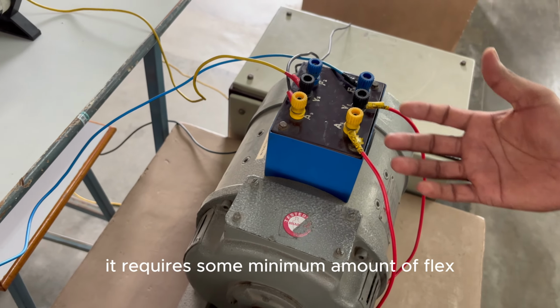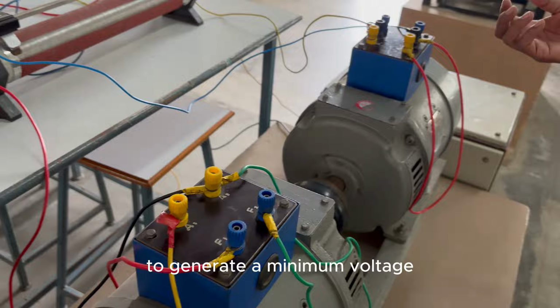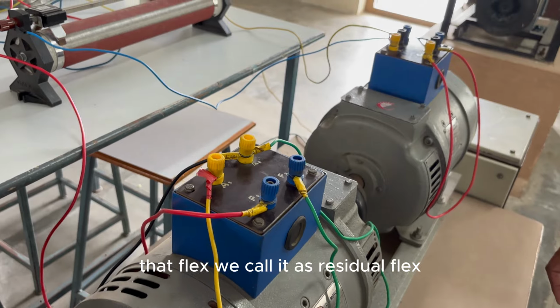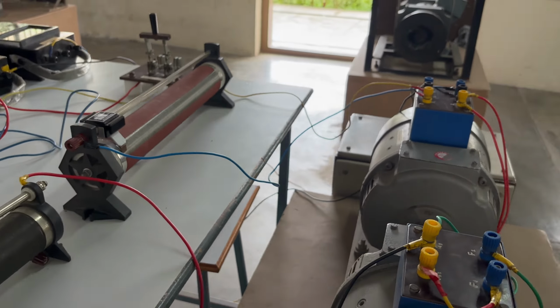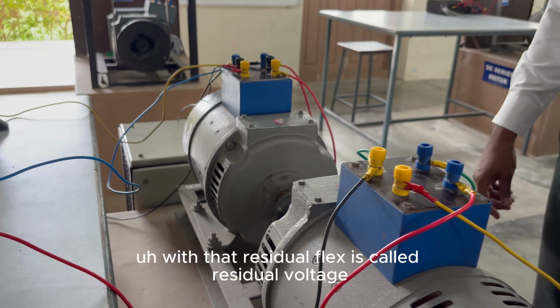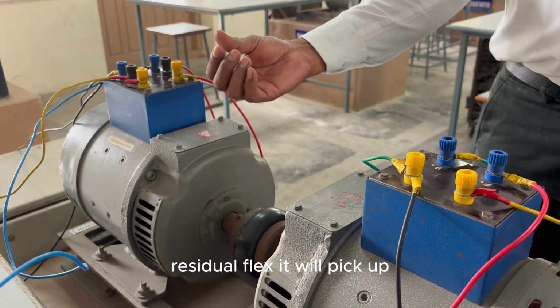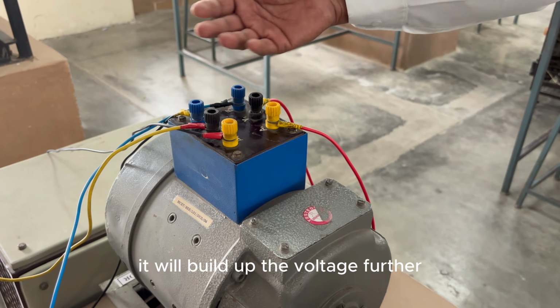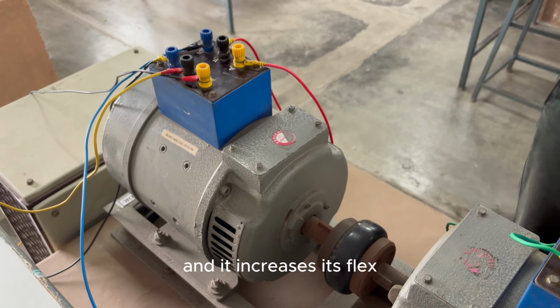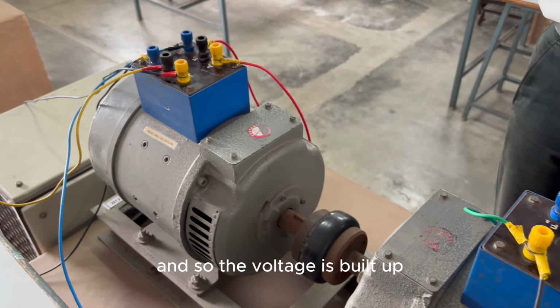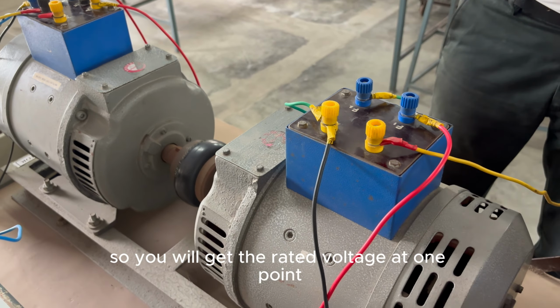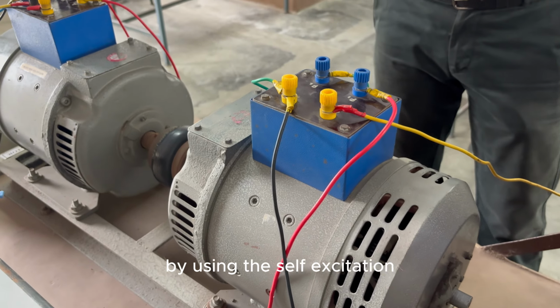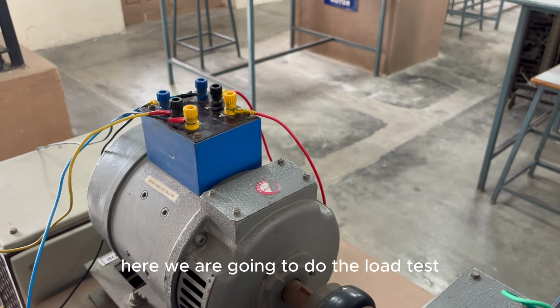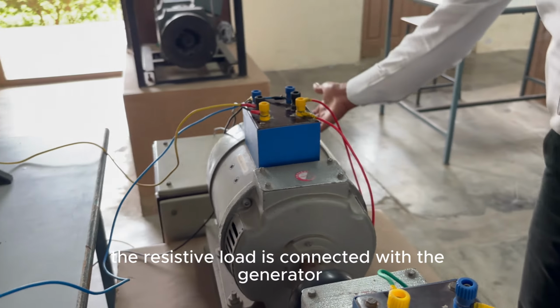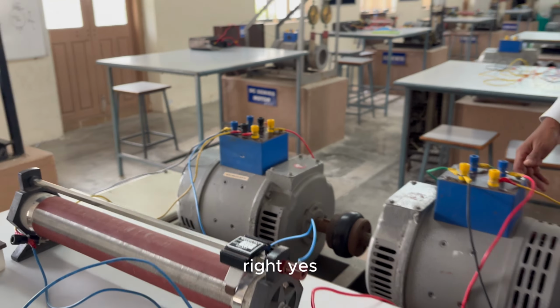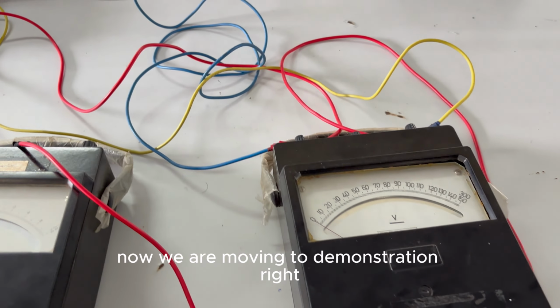At the start, it requires some minimum amount of flux to generate a minimum voltage. That flux we call residual flux, and the voltage generated with that residual flux is called residual voltage. With this small residual voltage and residual flux, it will build up the voltage further, increasing its flux, so the voltage is built up. You will get the rated voltage at one point by using self-excitation. Here we are going to do the load test, with a resistive load connected to the generator. Now we are moving to the demonstration.